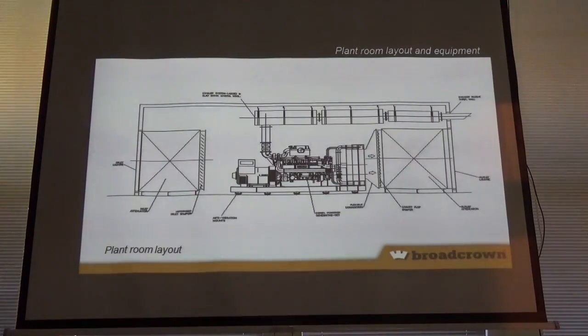And the other thing related to this is there's a clear distinction. Sometimes these are life safety units. And if they're life safety units, they recognise the likelihood is very low that they'll be needed. So they might actually turn around and say, okay, the nighttime figure is 65, give us one at 65, because they won't really care. But if it's a tenant's unit, with the likelihood of a longer running period, it's more onerous. That's what it tends to be, to be honest.